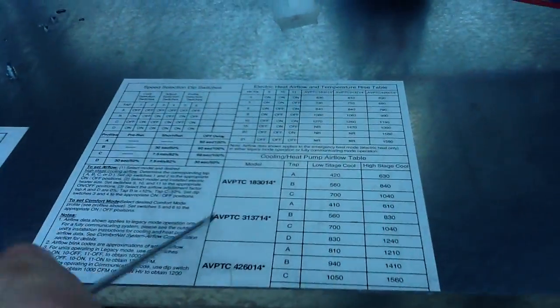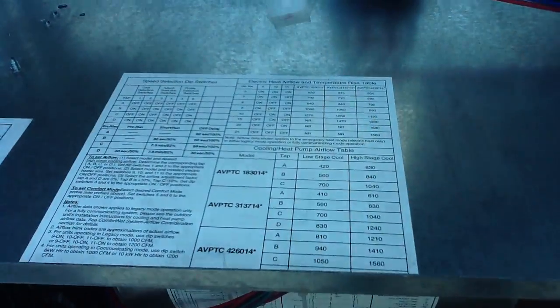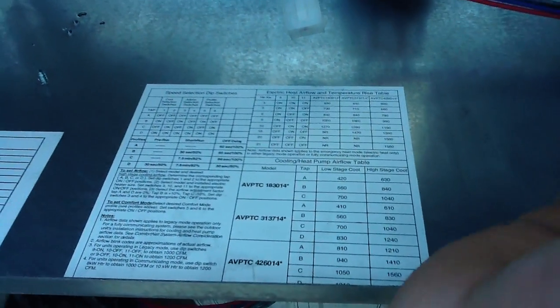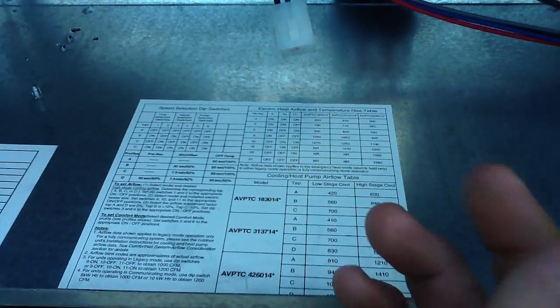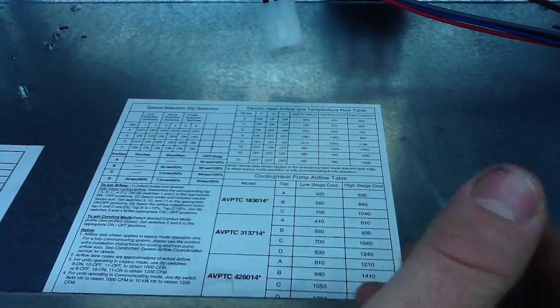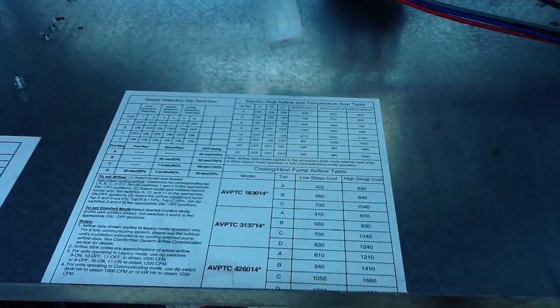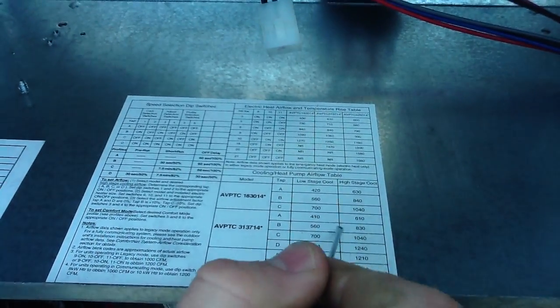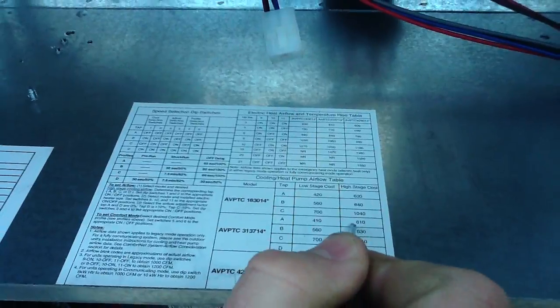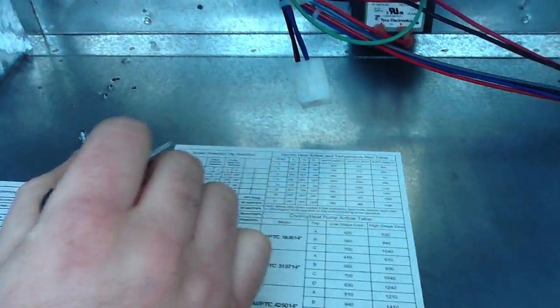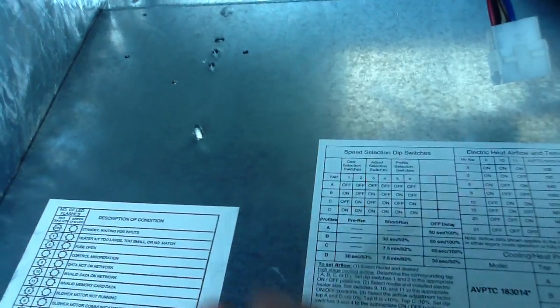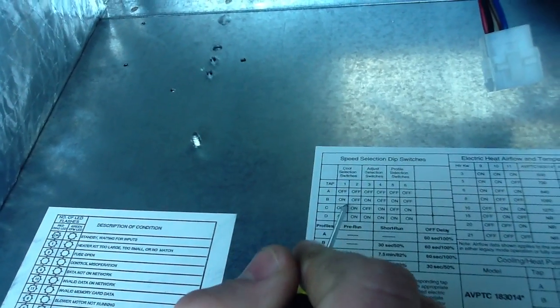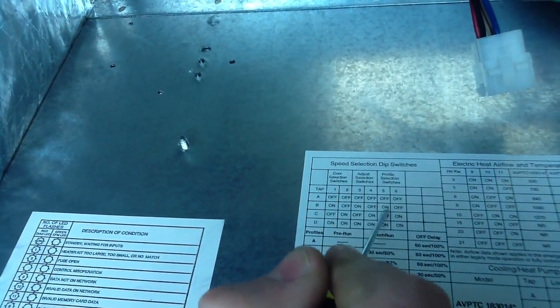Say you have two tons - go about 400 CFM per ton, times that by two, you'll get 800, so it's around 830. You go up here to B, because 830 is right here at B. You've got on, off, on, off, on, off.